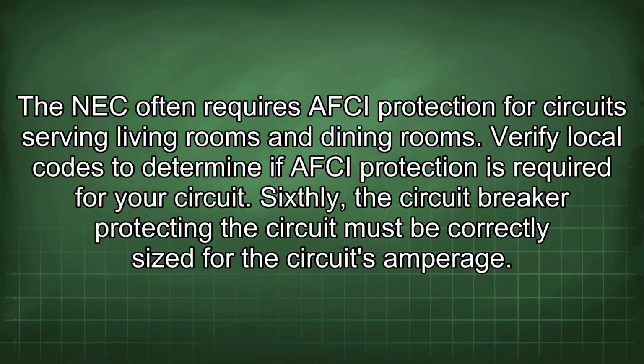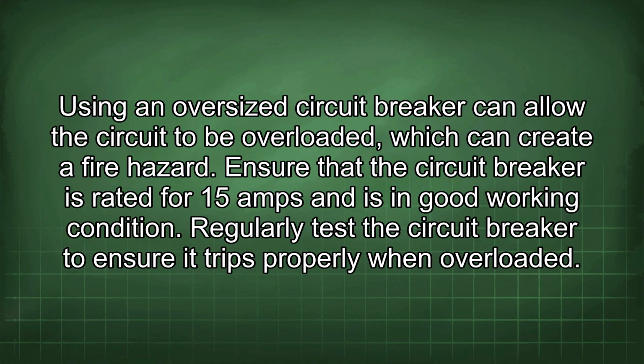Sixthly, the circuit breaker protecting the circuit must be correctly sized for the circuit's amperage. Using an oversized circuit breaker can allow the circuit to be overloaded, which can create a fire hazard. Ensure that the circuit breaker is rated for 15 amps and is in good working condition. Regularly test the circuit breaker to ensure it trips properly when overloaded.